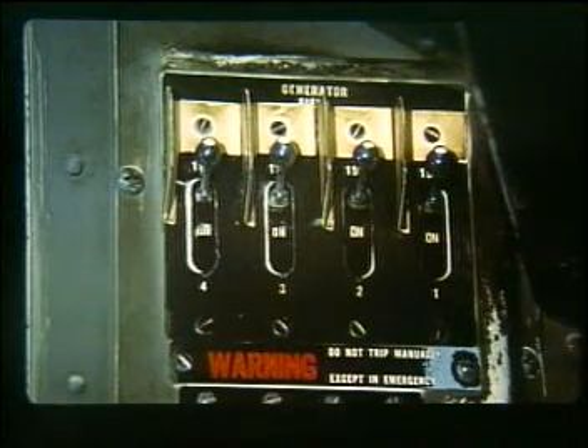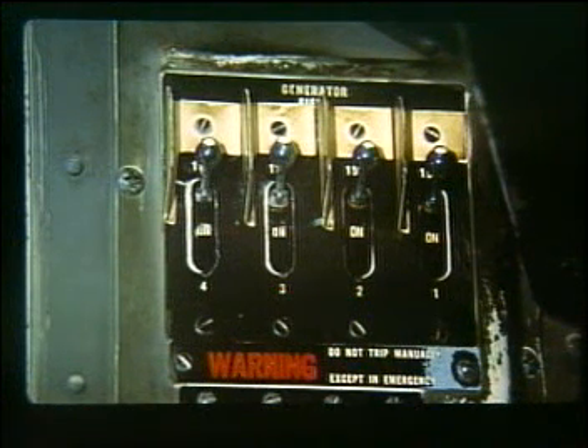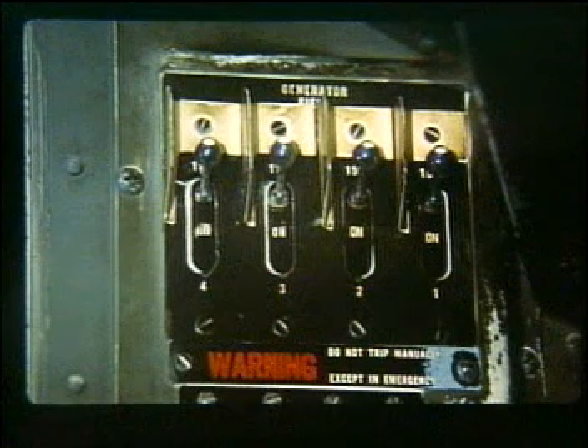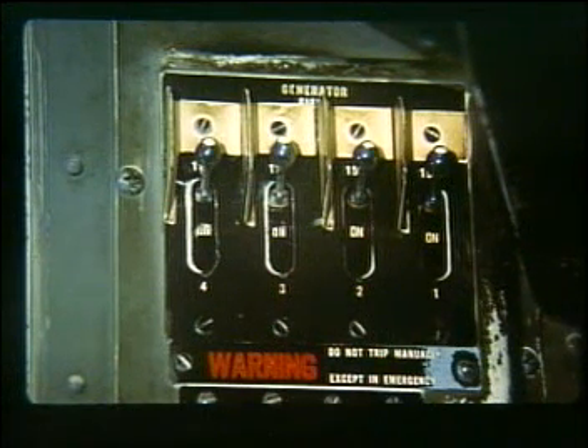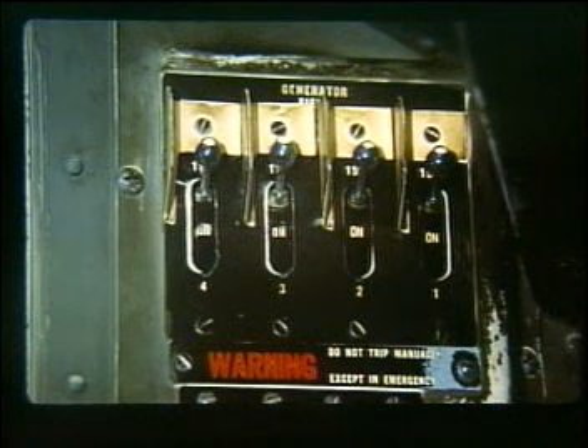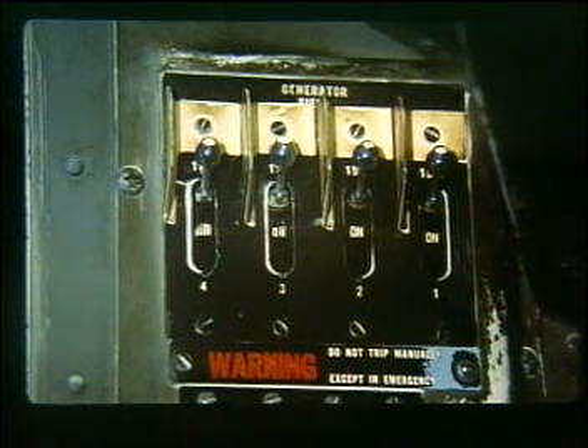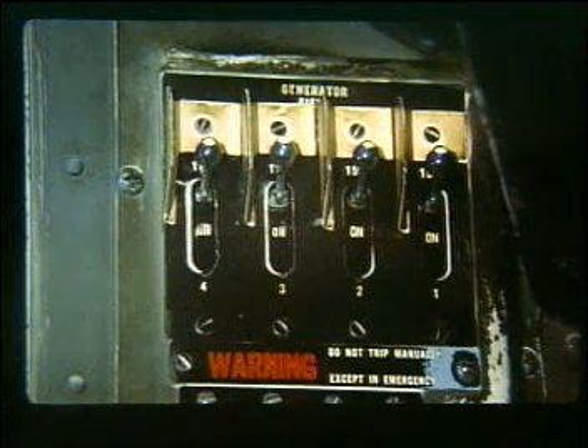The field circuit breakers, located on the right-hand side of the main circuit breaker panel, are trip-free magnetic type circuit breakers. They cannot be manually held in the on position in the event of an electrical malfunction. These breakers are used to isolate the generator field circuit during electrical malfunctions or troubleshooting.